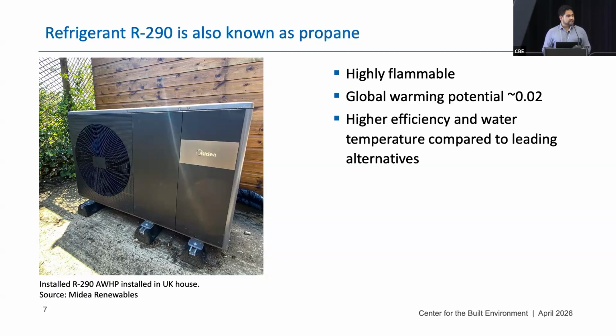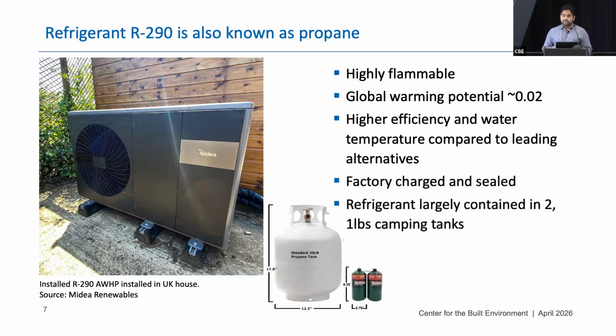To mitigate the risks associated with using propane as a refrigerant, the outdoor unit is installed outside, as you can see here, with no refrigerant lines running indoors. Water lines are used to distribute all that energy inside a home, like I showed in the previous slides. So all the propane is contained within this monoblock, and furthermore, the refrigerant is factory charged and sealed, so HVAC technicians don't have to charge the unit in the field.